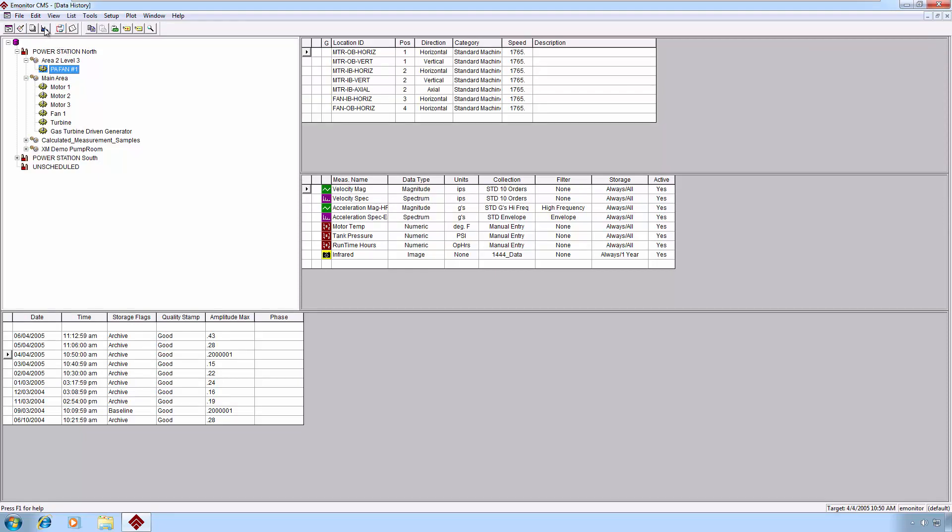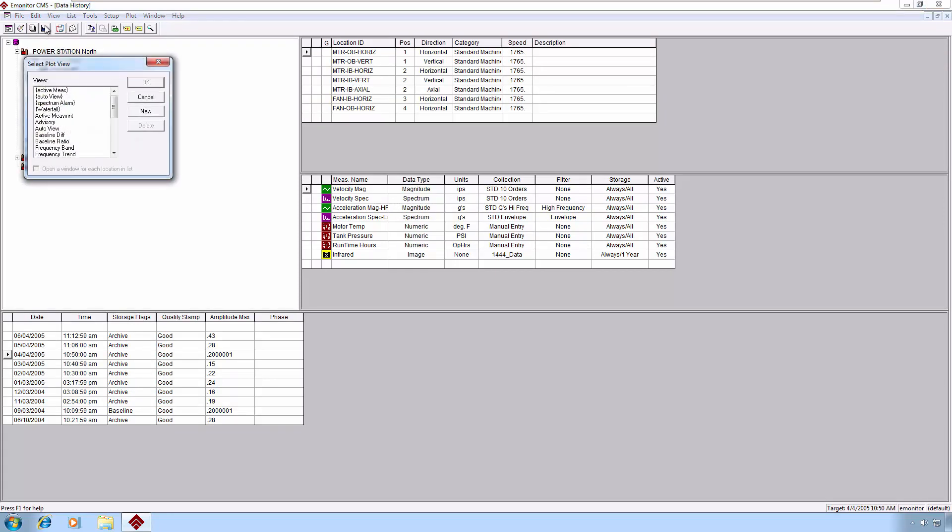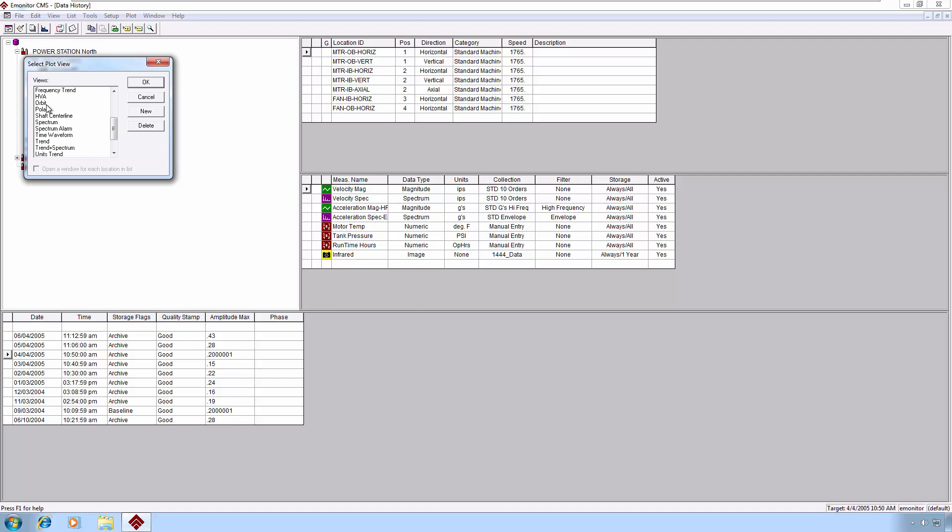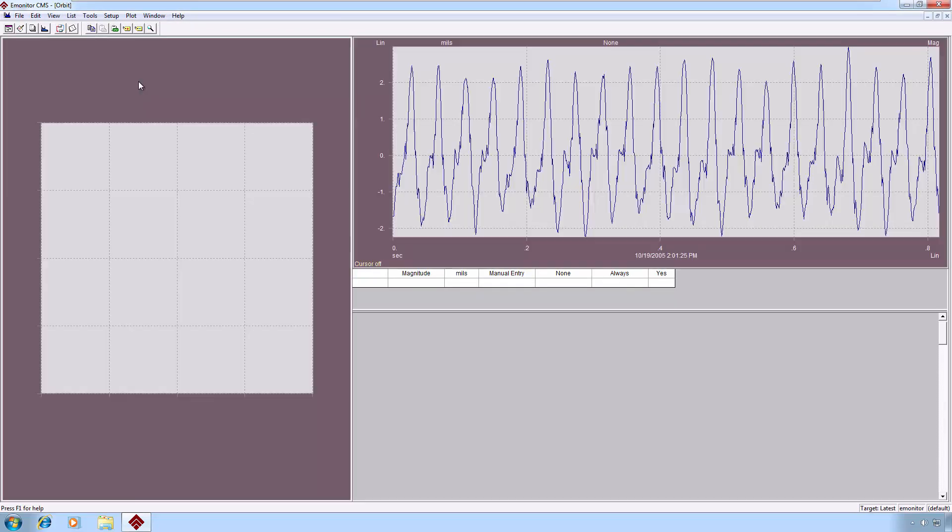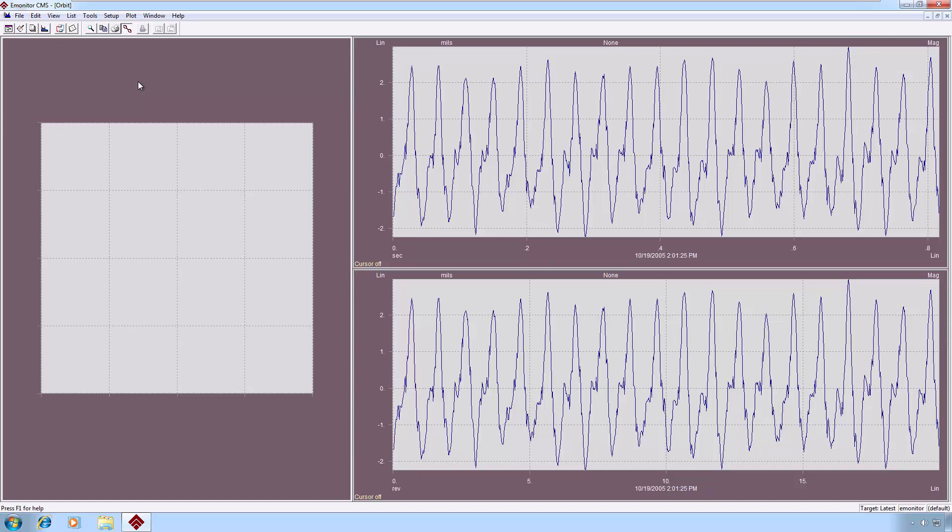Let's take a look next at orbit plots. In order to view an orbit plot, we need to have two synchronized time waveforms in an X and Y orientation. And we have our two time waveforms. Now for these to display properly, we have to tell the polar plot part of the view in our options by double clicking in the margin here, which time waveform measurement is which.